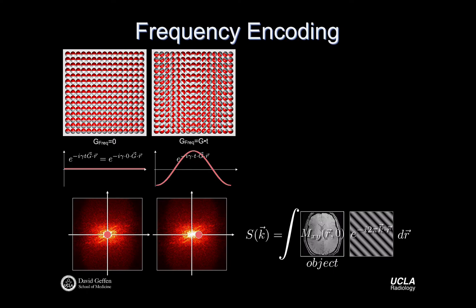And now I can turn on my receiver again and say, well, how much of that pattern do I have in my underlying object? And I can measure and record the amplitude of that, the state of the magnetization when that pattern is printed on my magnetization. Now, what makes one image different from another image is not this pattern that we print, but the magnitude or presence of that pattern in the underlying object. And that in turn will depend on the T1 and T2 at this point, and the T1 and T2 at this point, and the proton density in the T1 and the T2 at this point. So whether or not you have a lot of that pattern depends on how you manipulate the contrast to begin with.